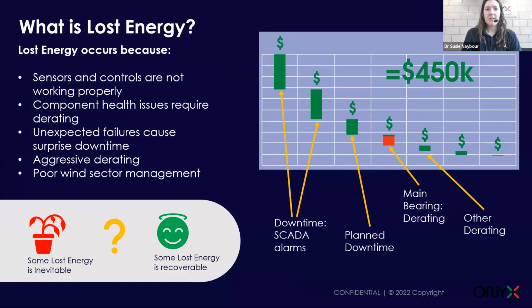In the first case, you might see performance losses because sensors or controls on the system are not working properly. For example, you may have an anemometer that becomes miscalibrated, which means your wind turbine is shutting down when it shouldn't be. If the sensor is reading higher than true, it might shut down in the high wind period, which would lose you quite a lot of production because that's when the turbine should really be operating at its maximum.